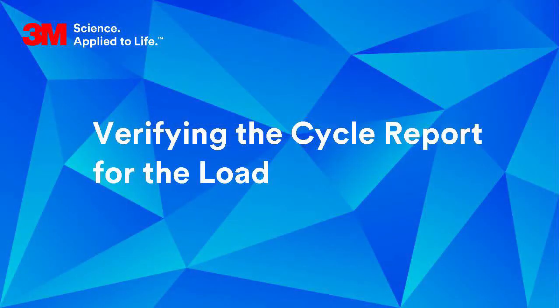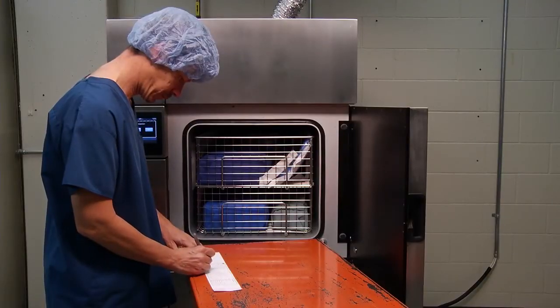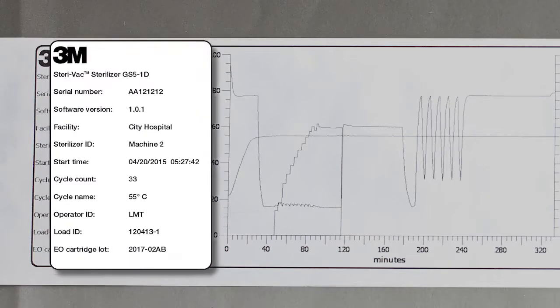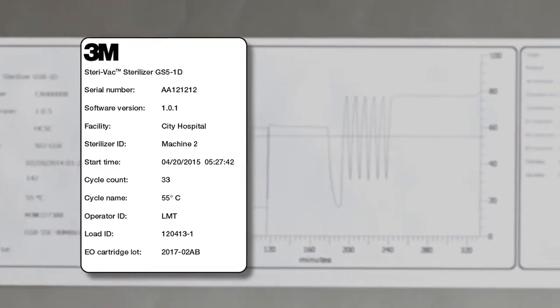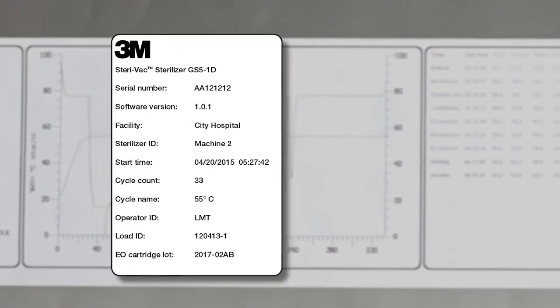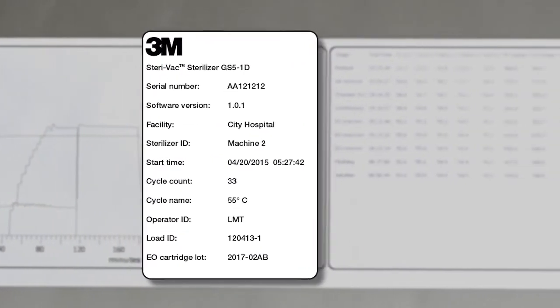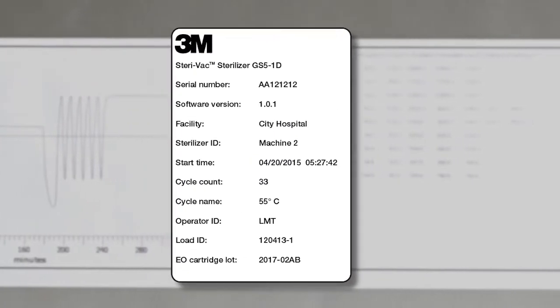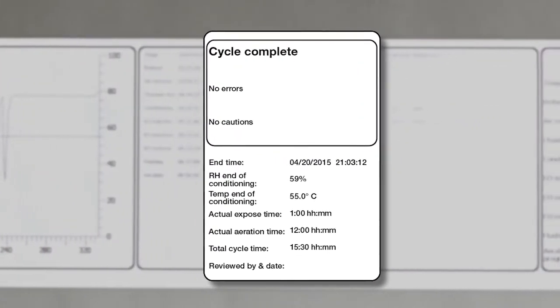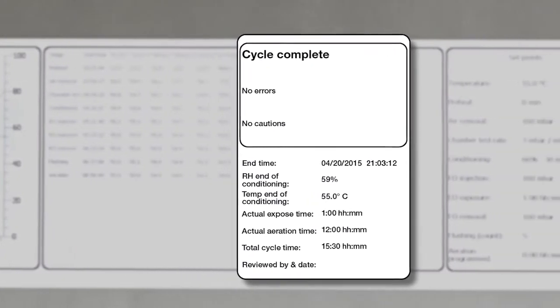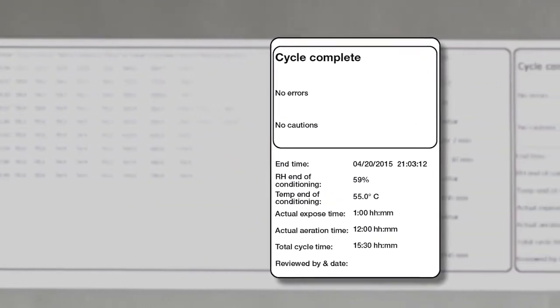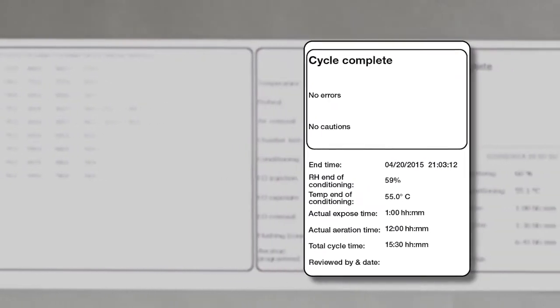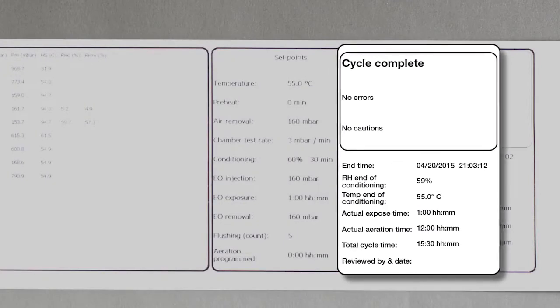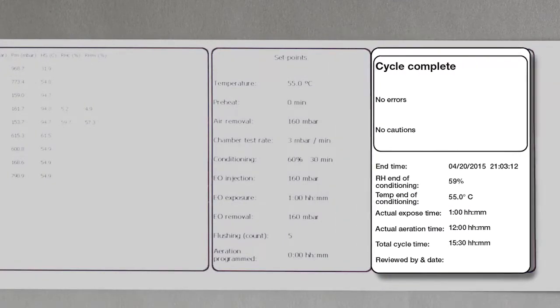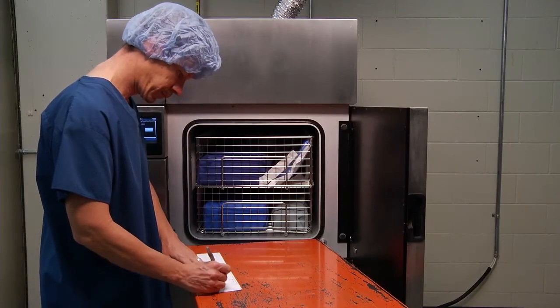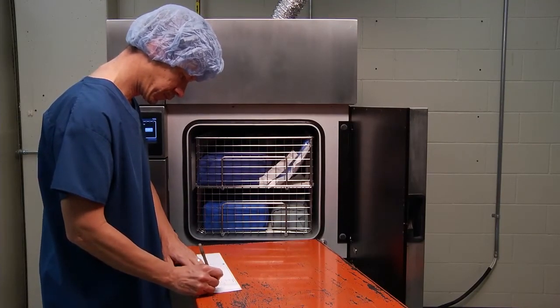Before you remove the load from the chamber, verify the following items on the cycle report. In the cycle report header, verify that the start time, date, operator ID, and cycle name are correct. If you created a load ID, verify that the load ID matches your records. In the cycle report footer, verify the final status indicates cycle complete. Verify there are no errors or cautions. Verify the %RH and temperature at the end of conditioning meet the specifications in the operator manual. And verify that the actual ethylene oxide exposure time and actual aeration time are correct per the manufacturer's instructions for use.